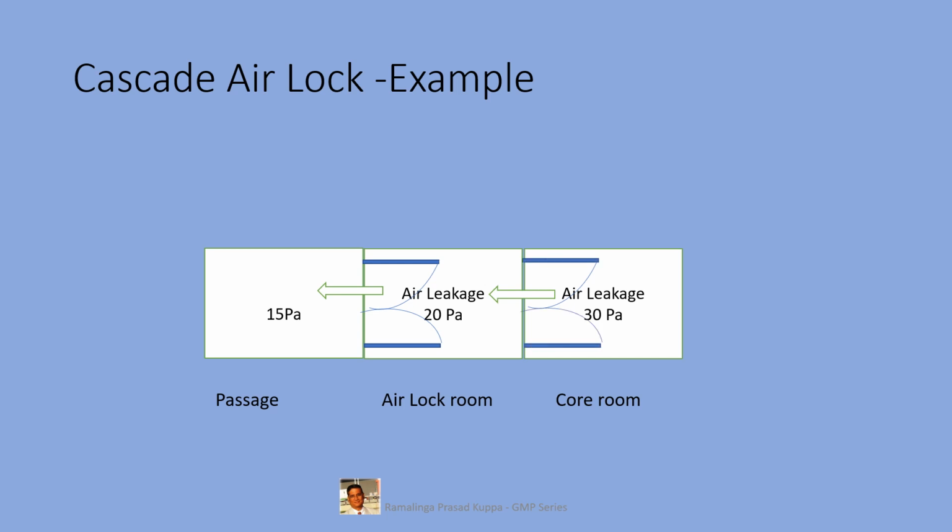See this design. The concept is simple to understand. The door will try to keep in closed condition always because of the pressure exerted on the doors. If the doors open to the lesser pressure areas, the doors would tend to open under higher pressure. I hope it is not too complicated to understand this simple principle.